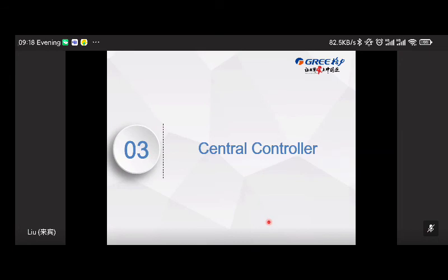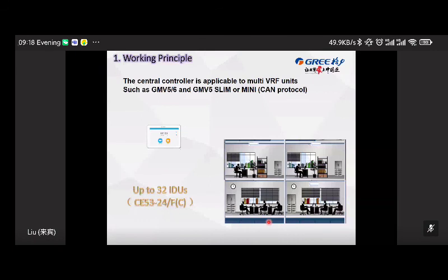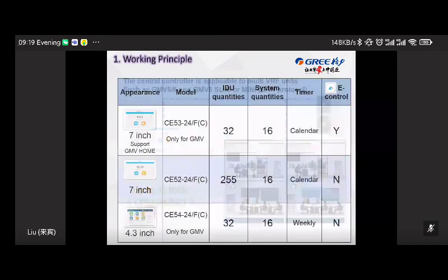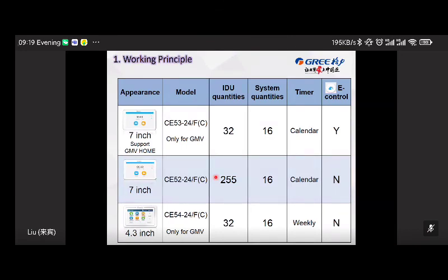Okay, for VRF, the central controller is almost necessary to improve the management of the whole system. And for the central controller, it is now applicable for GMV5, GMV6, Slim, or Mini CAN protocol units. You can use this one, CE53. However, except for CE53, currently we have 3 central controllers. The first one is 7-inch. The maximum quantity is 32 indoor units. Yeah, not a lot, just 32 units maximum. The system quantity is 16, counting the timer.